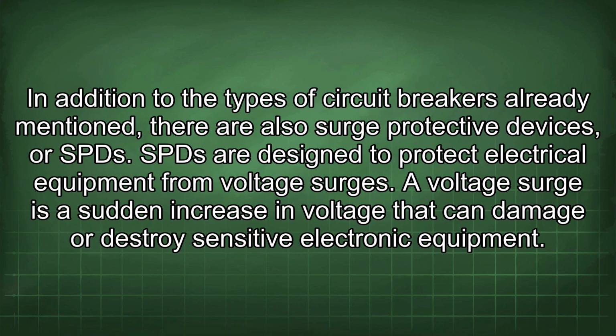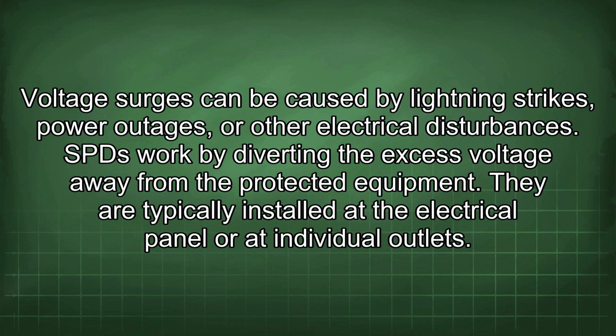In addition to the types of circuit breakers already mentioned, there are also surge protective devices, or SPDs. SPDs are designed to protect electrical equipment from voltage surges. A voltage surge is a sudden increase in voltage that can damage or destroy sensitive electronic equipment. Voltage surges can be caused by lightning strikes, power outages, or other electrical disturbances. SPDs work by diverting the excess voltage away from the protected equipment. They are typically installed at the electrical panel or at individual outlets.